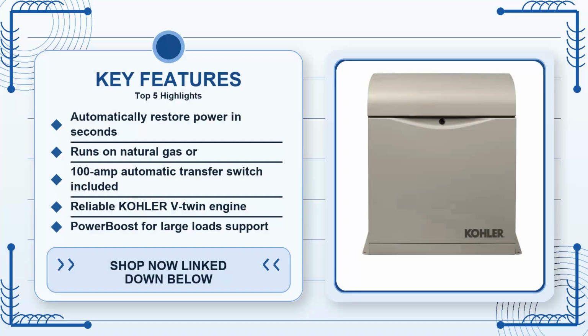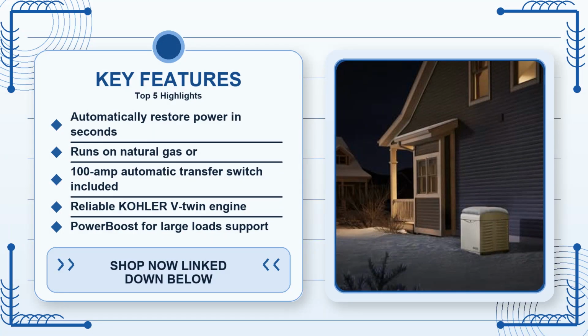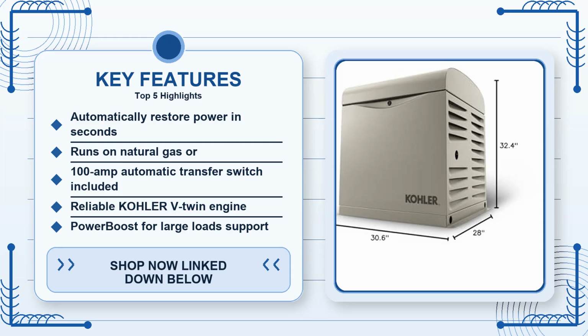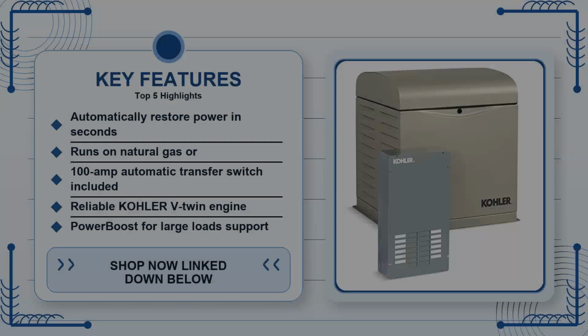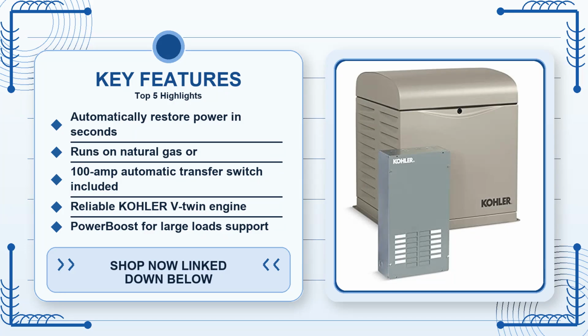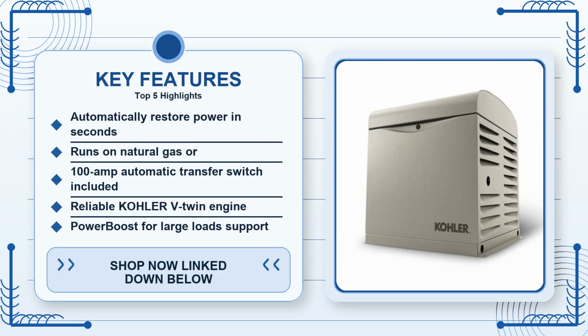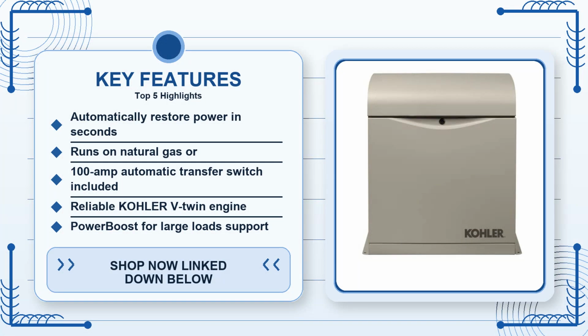Practical strengths, summarized without rehashing the same point, include the rapid 10-second start, dual fuel versatility, and the 12-circuit ATS that lets you prioritize loads. The PowerBoost feature isn't just a buzzword, it actually lets the engine handle the high inrush current that a central air compressor demands, preventing the common generator stalls when AC turns on problem. Because the ATS is indoor rated, you can install it close to the main panel, reducing voltage drop and making the wiring run shorter and cleaner.